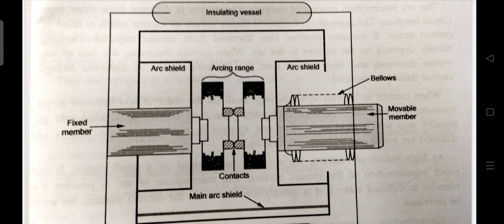The outstanding feature of a VCB is that it can break any heavy fault current perfectly just before the contacts reach the defined open position. The application of VCB is for a country like India where distances are quite large and accessibility to remote areas difficult. The installation of such outdoor maintenance free circuit breaker should prove a definite advantage. VCBs are being used for outdoor application ranging from 22 kV to 66 kV. Even with limited range of 60 to 100 MVA, they are suitable for majority of application in rural areas.